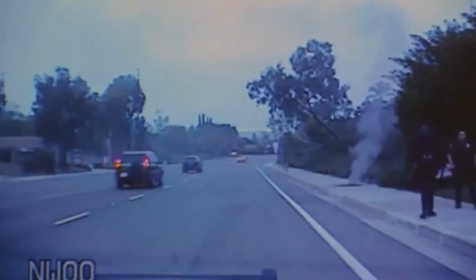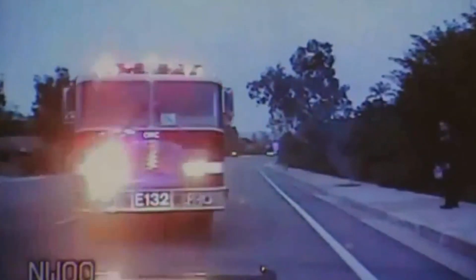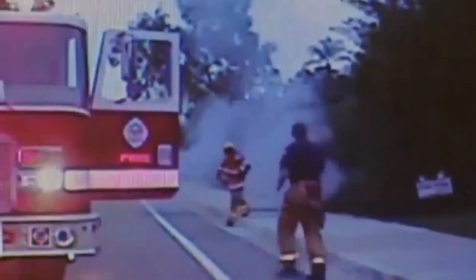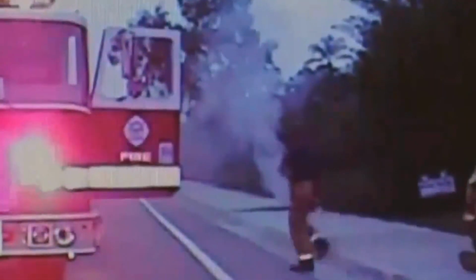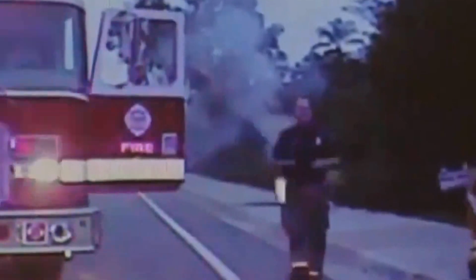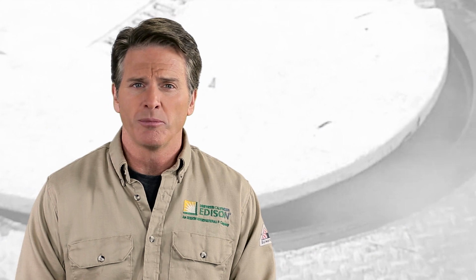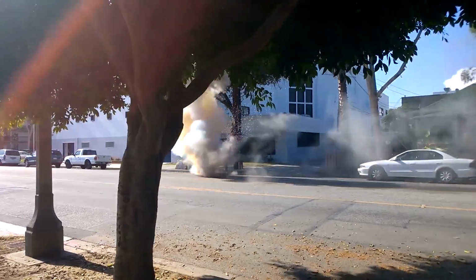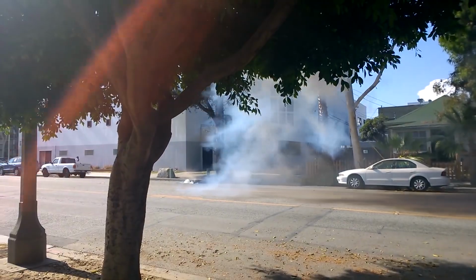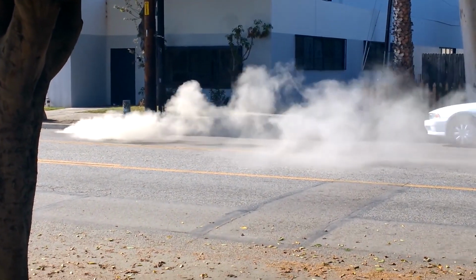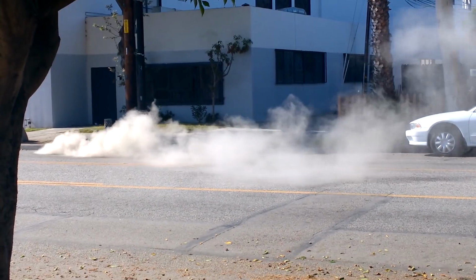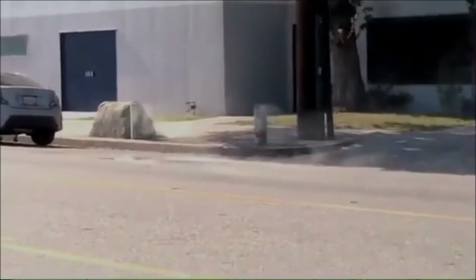Emergencies involving underground manholes or vaults are high-risk situations for first responders, even if the appearance above ground looks normal. If flammable gases are present in the manhole, removing the cover could provide enough oxygen or sparking to cause an explosion. If gases are present in the cable ducts that run from manhole to manhole, there could be additional explosions in adjacent manholes. If an underground transformer in the vault has failed and the oil is above the ignition temperature, it could explode without notice. In the underground environment, one failure in the system has the capacity to cause additional equipment or cable failures. The resulting explosions could seriously harm you and others nearby.